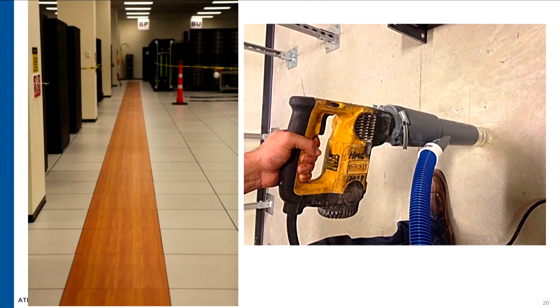With the Blue Gene Q system, the vendor had given us an estimated weight, and we said great, that works fine in our data center. Maybe 9 months before the machine was due to be delivered, the vendor called and said, well, we've got some hardware now, and it's going to weigh a little bit more. So we went out and looked, and this is a 4-foot raised floor, and if one of these racks goes into that floor, somebody could be seriously injured.